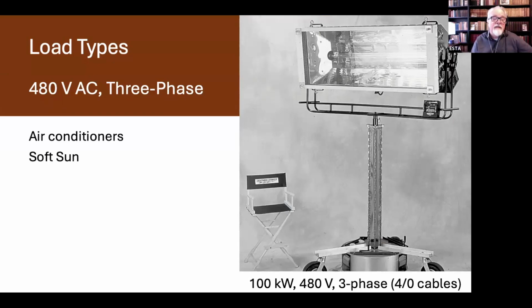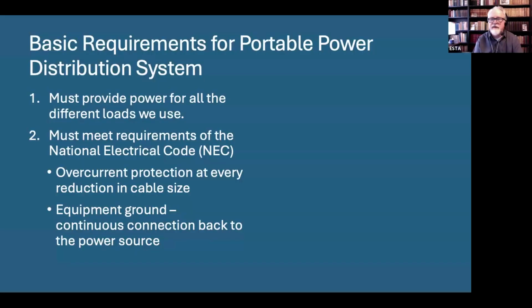The last thing you might have is a 480 volt AC 3-phase load, which big air conditioners commonly are, and this 100 kilowatt Soft Sun unit. Now you could run this Soft Sun at a lower voltage, but the biggest cable that's portable is 4-aught cable. You call it portable because it's 100 pounds, which is just barely portable. But if this was anything less than 480, you would have to have a bigger cable than that, which would not be portable. So those are the kinds of loads.